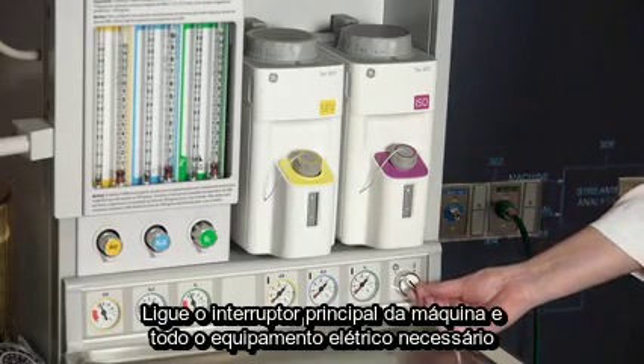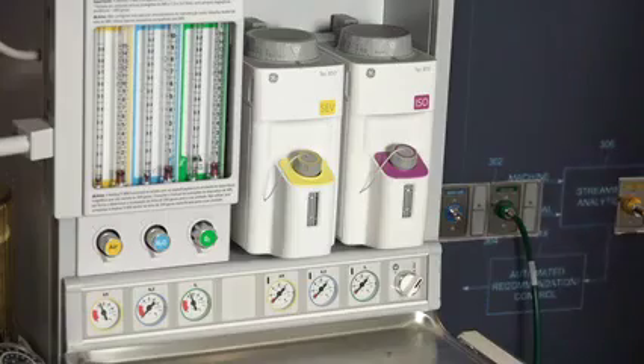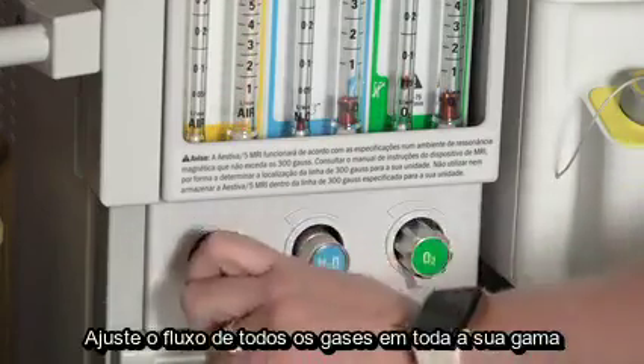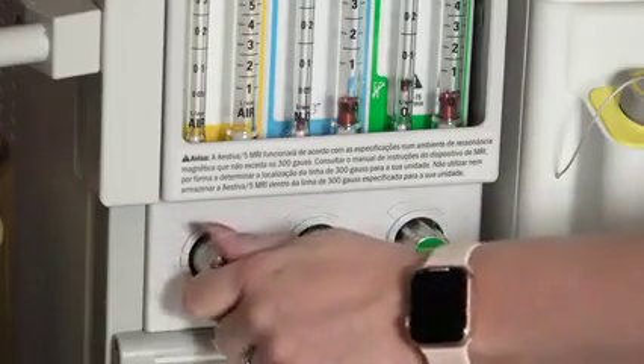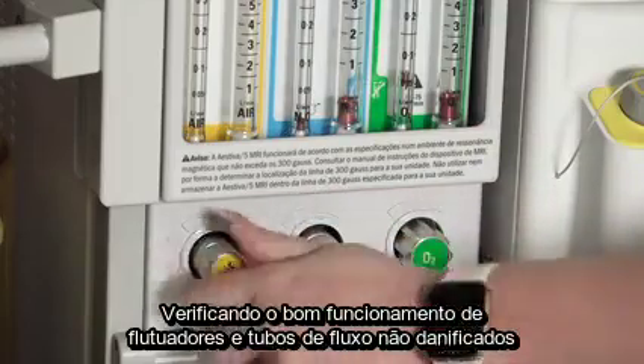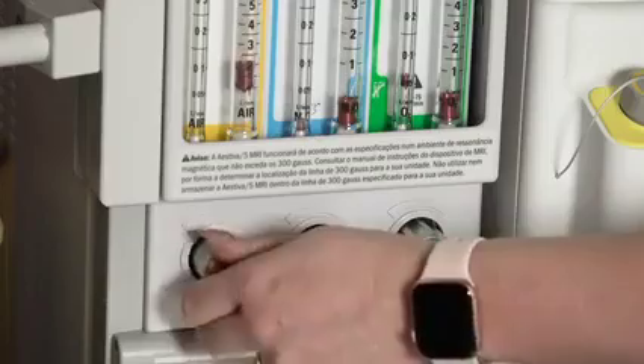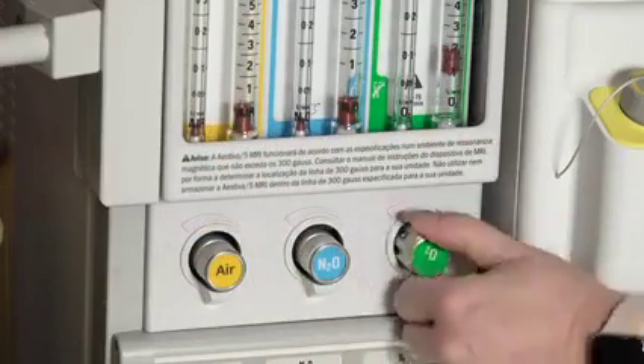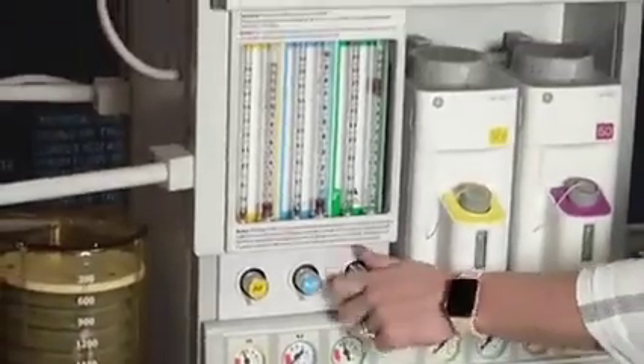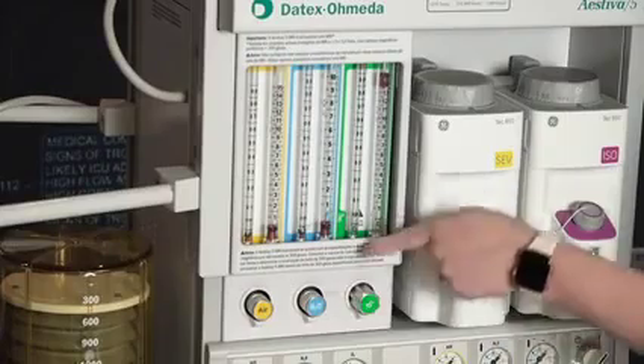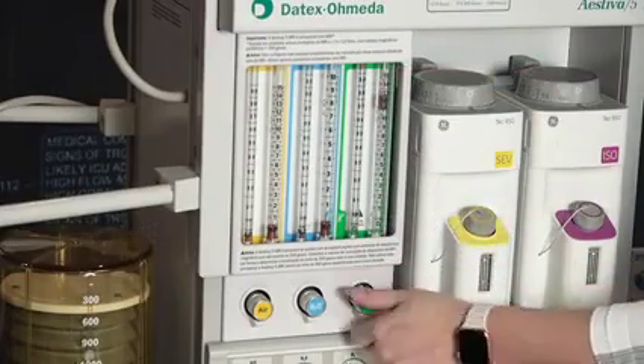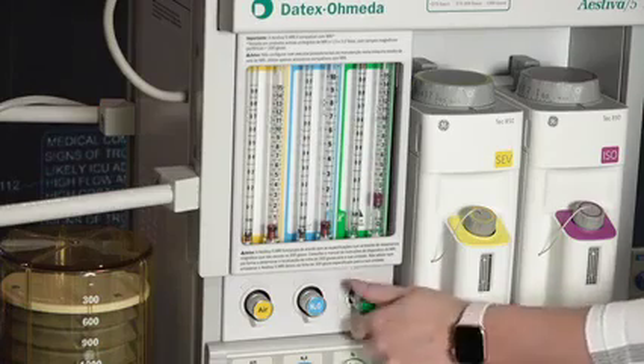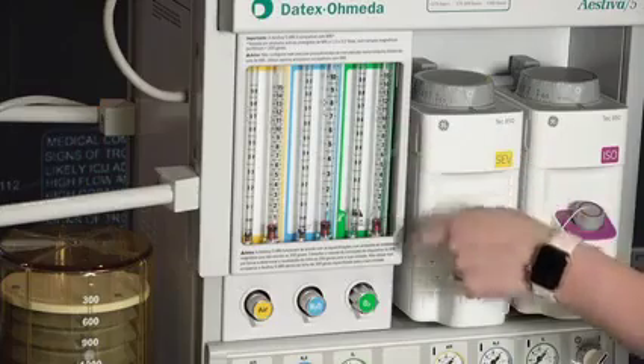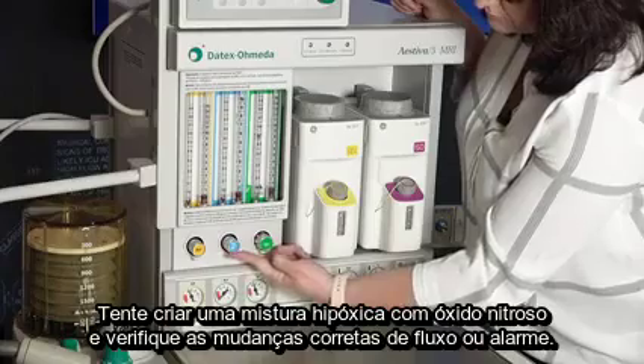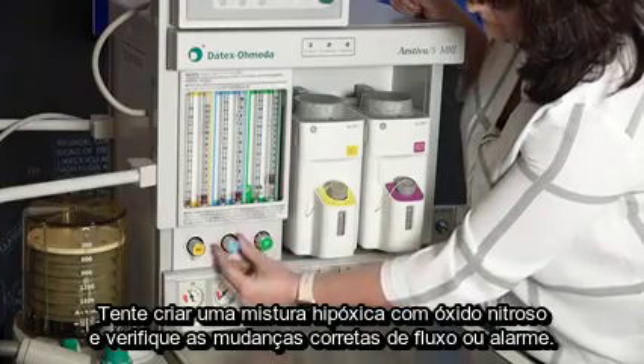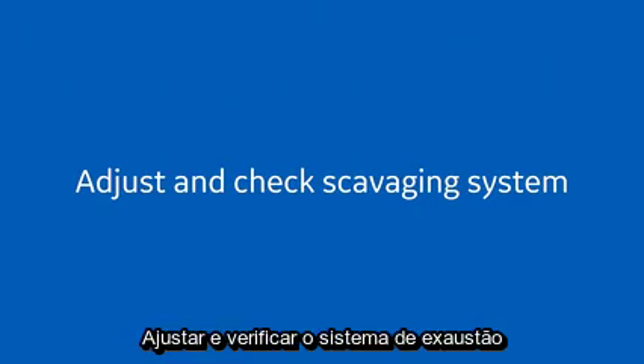Turn on the machine master switch and all necessary electrical equipment. Test your flow meters. Adjust the flow of all gases through their full range, checking for smooth operation of floats and undamaged flow tubes. Attempt to create a hypoxic oxygen nitrous mixture and verify correct changes in flow and/or alarm. Adjust and check the scavenging system.